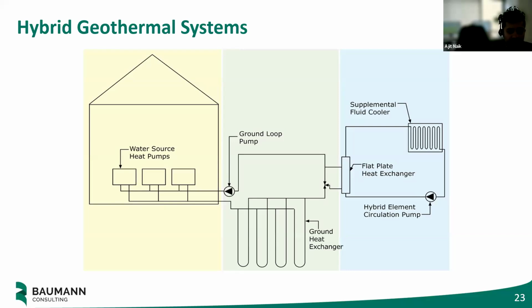For those who know the Pareto principle, sometimes you get 80% of the results for 20% of the effort. This is one of those cases. Even if you design a geothermal system to meet only part of your load, you still need a little supplemental heat rejection, like a dry cooler, or supplemental heat addition, like a small electric boiler. Usually you don't size these full, you're not providing a full-size fluid cooler or a full-size pony boiler.